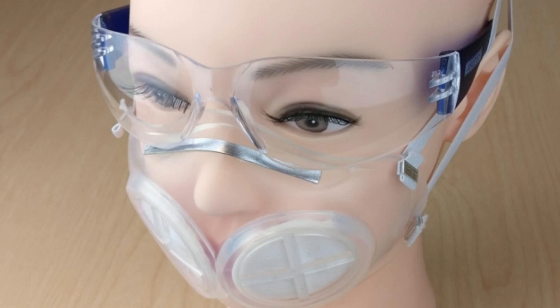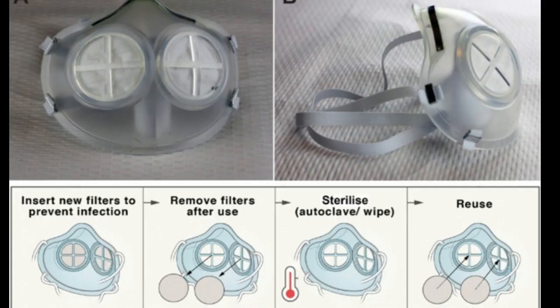To test the comfort and fit of the mask, the researchers recruited about 20 healthcare workers and had each subject perform the standard fit test for N95 masks. During this test, the subject puts the mask on and then performs a series of movements to see if the mask stays in place. A nebulized sugar solution is sprayed in the room, and if the subject can taste or smell it, it means the mask is not properly fitted. All 20 subjects passed the fit test, and they reported that they were able to successfully insert and remove the N95 filter. When asked their preference between the new mask, a typical N95 mask, and a standard surgical mask, most either said they had no preference or preferred the new silicone mask. They also gave the new mask high ratings for fit and breathability.